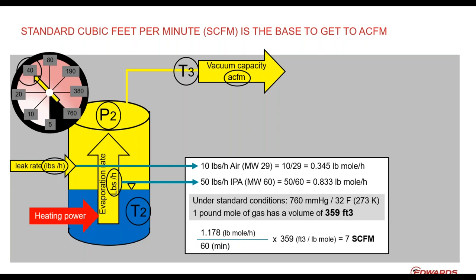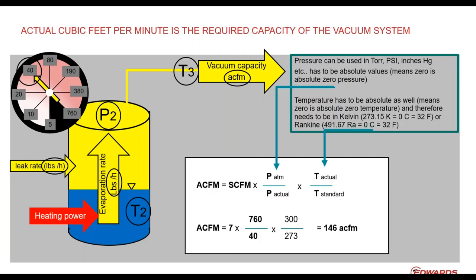In this example, we land at 7 standard cubic feet per minute (SCFM) — that's the firm ground to stand on. Standard cubic feet per minute is the volumetric equivalent of the mass flow at standard conditions — atmospheric pressure and 32°F. Actual cubic feet per minute (ACFM) is where the vacuum pump lives; that's the design point for the vacuum pump. SCFM is corrected by two values: instead of standard pressure, we use actual pressure, and instead of standard temperature, we use actual temperature. That's how you convert SCFM to ACFM.